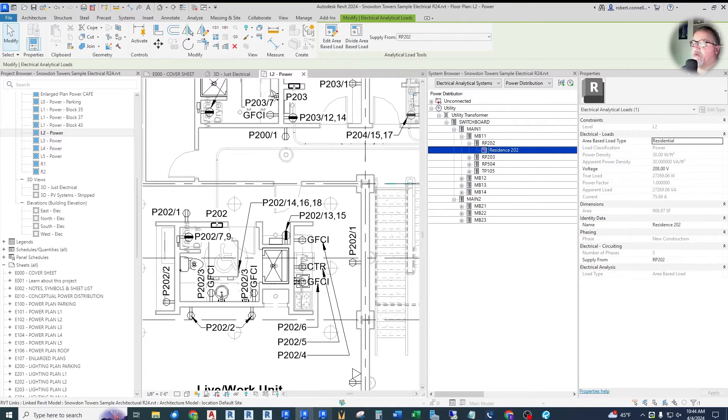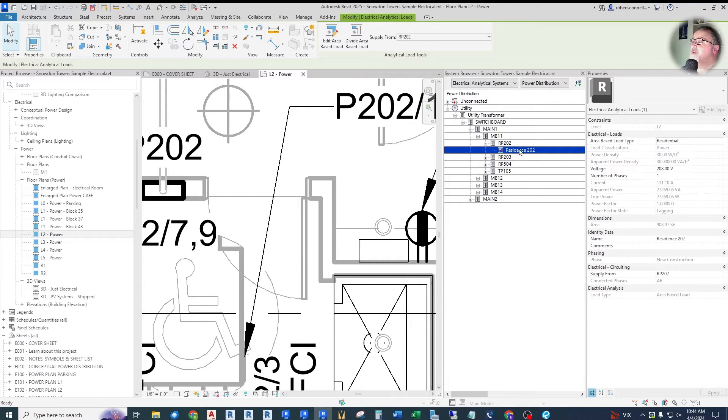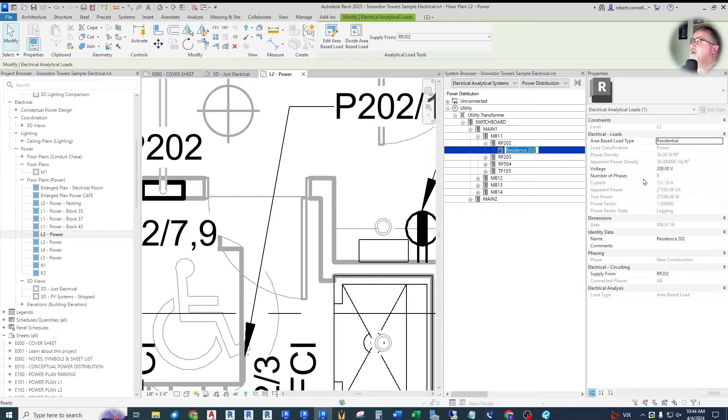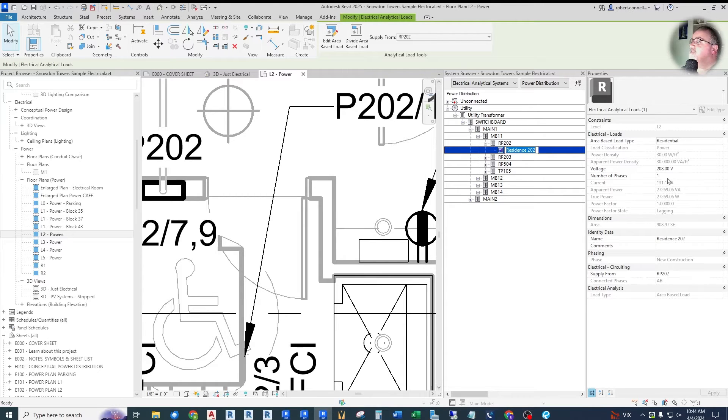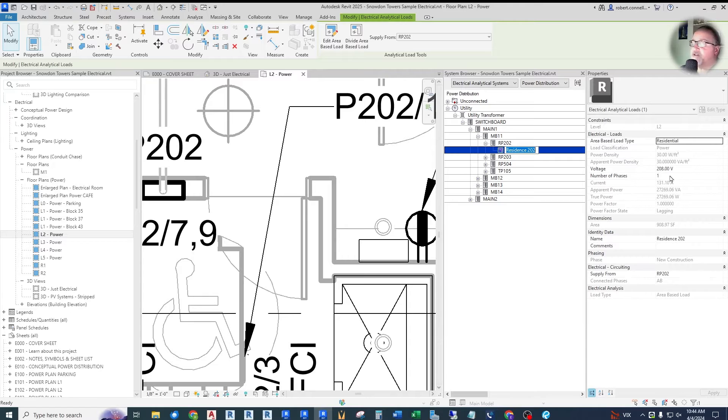Look over at Revit 2025 now, the same system, the same Residence, 202, now says 208, and you have a number of phases option. So now we can go single phase and it gets calculated at the 131 amps. As you can see, the amps are higher because the loads only spread across the two phases.